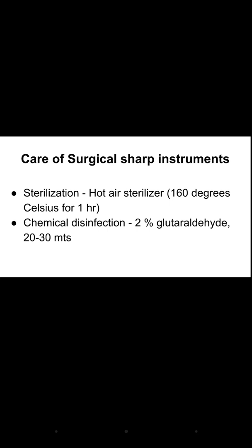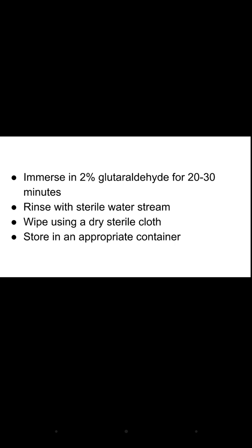So all these stainless steel instruments, if they have been used, should first be cleaned with water. Ensure that all the blood, tissue and organic matter is removed. Then immerse them in the 2% glutaraldehyde solution for 20 to 30 minutes. After this disinfection, rinse them with a stream of water, then wipe using a dry sterile cloth, and then store in the appropriate container. So after using, wash them in a stream of water, and after washing, immerse them in the Cidex solution and then rinse again.